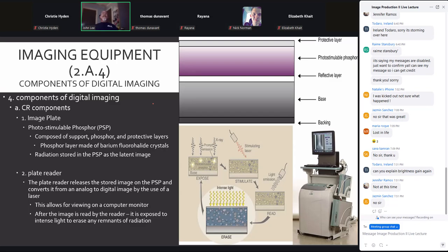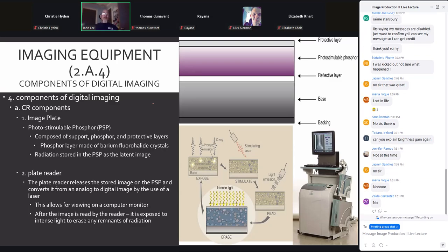So digital, very first system that we came up with, invented in the 70s. Kodak, first company to come up with CR, actually, which was kind of ironic because Kodak was huge in X-ray film. But they came up with CR first. Fuji came out with the system clinically in 82. But Kodak started it, but Fuji came out with it clinically. Great systems too. Comprised of an image plate which is coated with a photostimulable phosphor. So we call it a photostimulable phosphor plate.